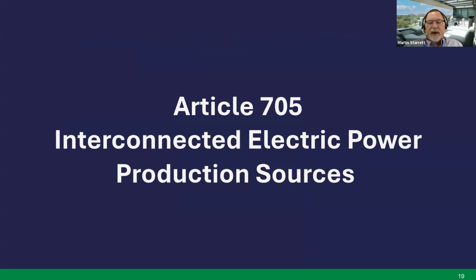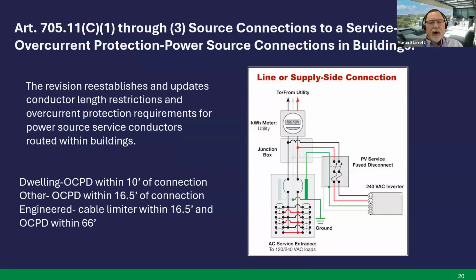Article 705, interconnected electric power production sources. So Article 705.11C 1 through 3, source connections to an emergency, source connections to service overcurrent protections, power source connections in building. The revision reestablishes and updates conductor length restrictions and overcurrent protection requirements for power source service conductors routed through buildings. This was originally, I believe, in 2020, and then it was removed in 23, so it's brought back.